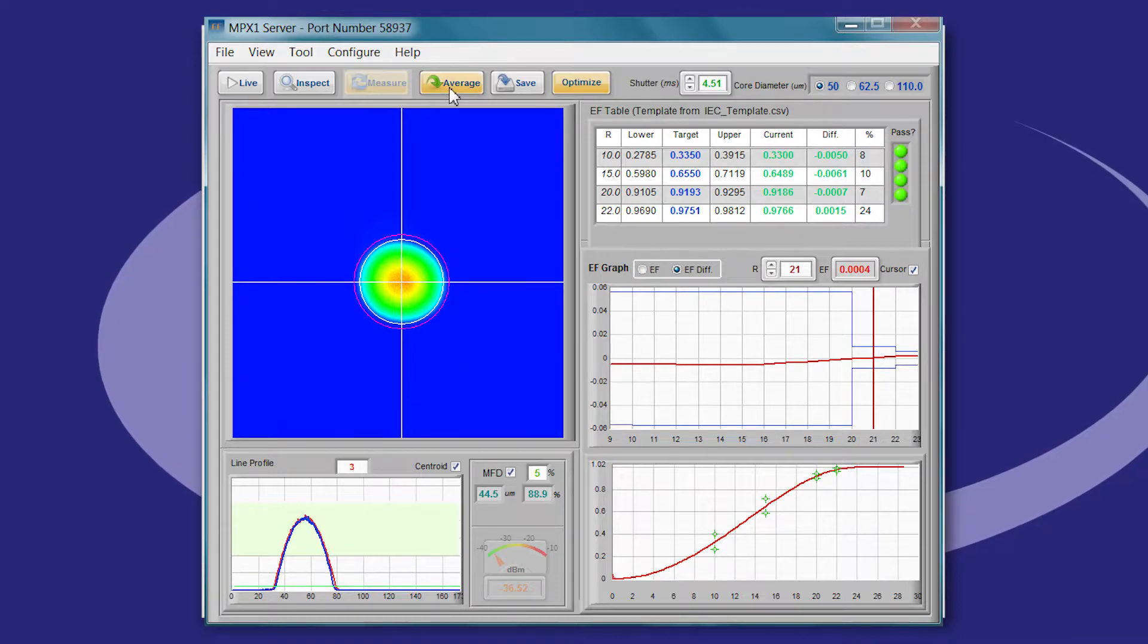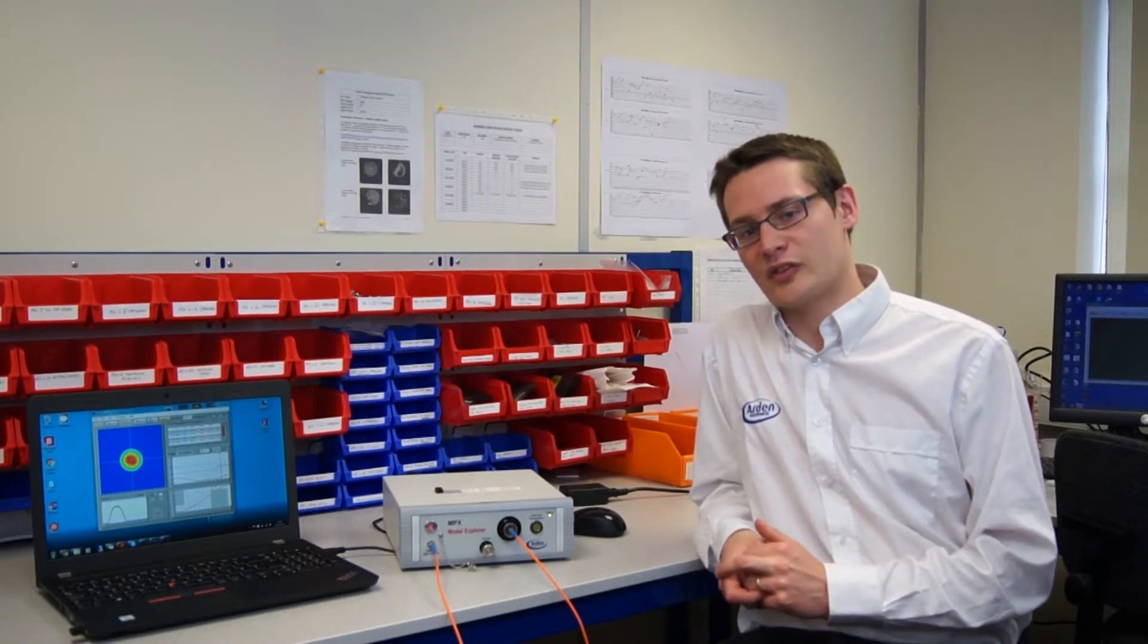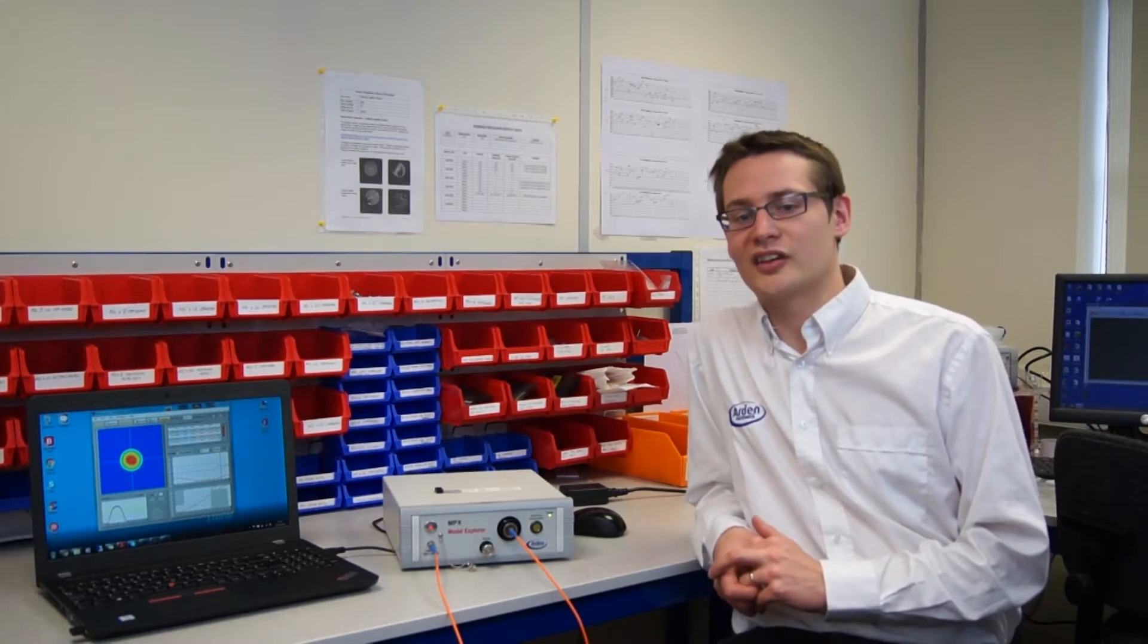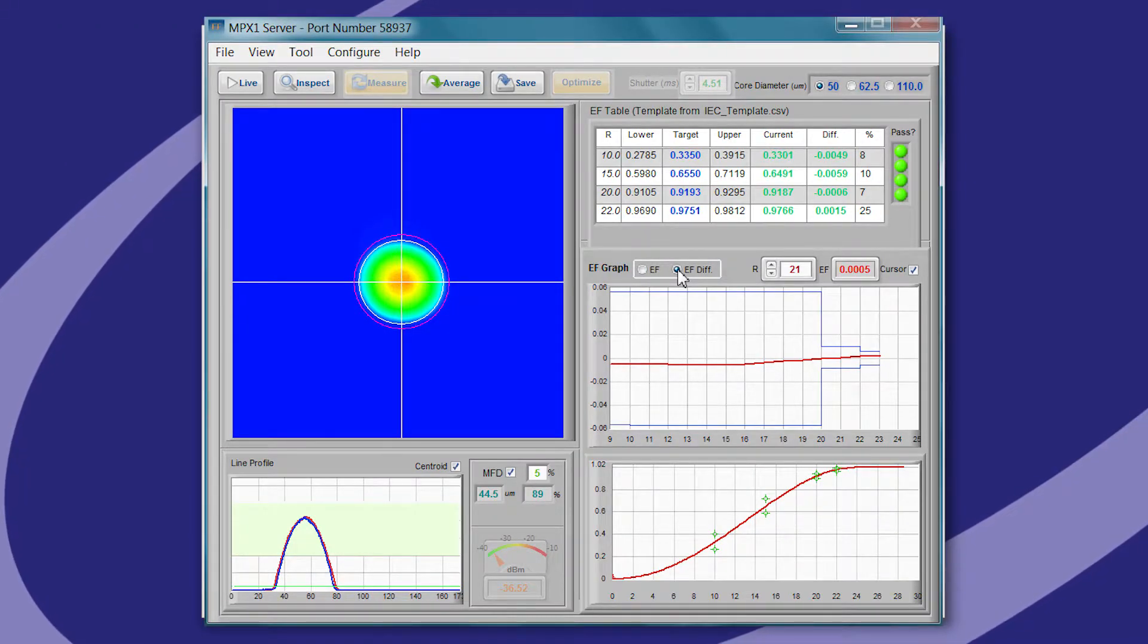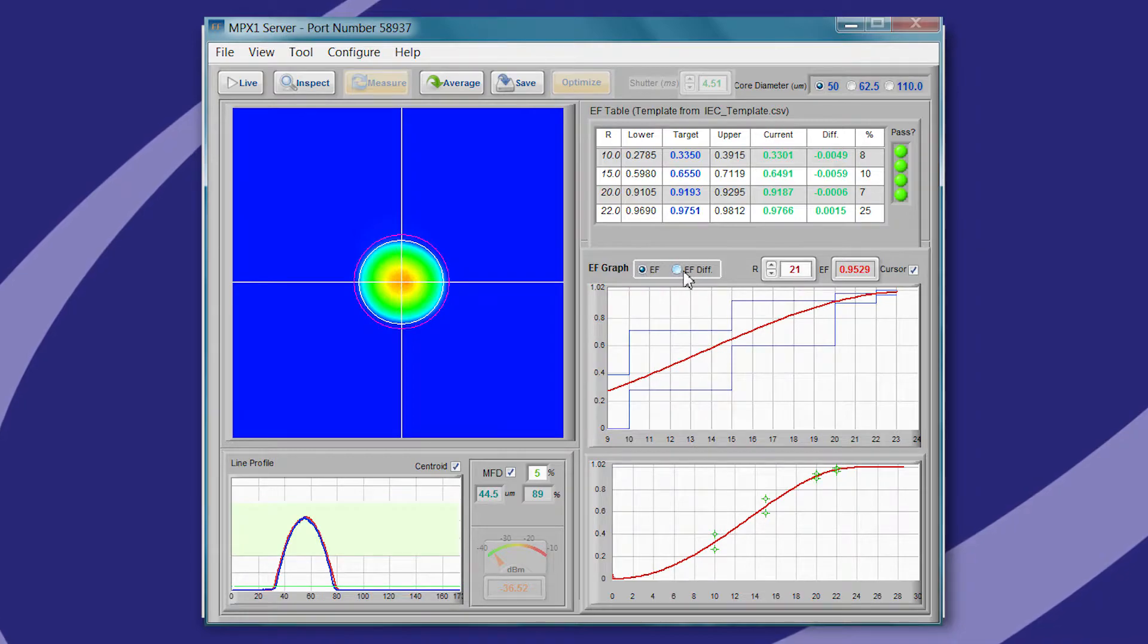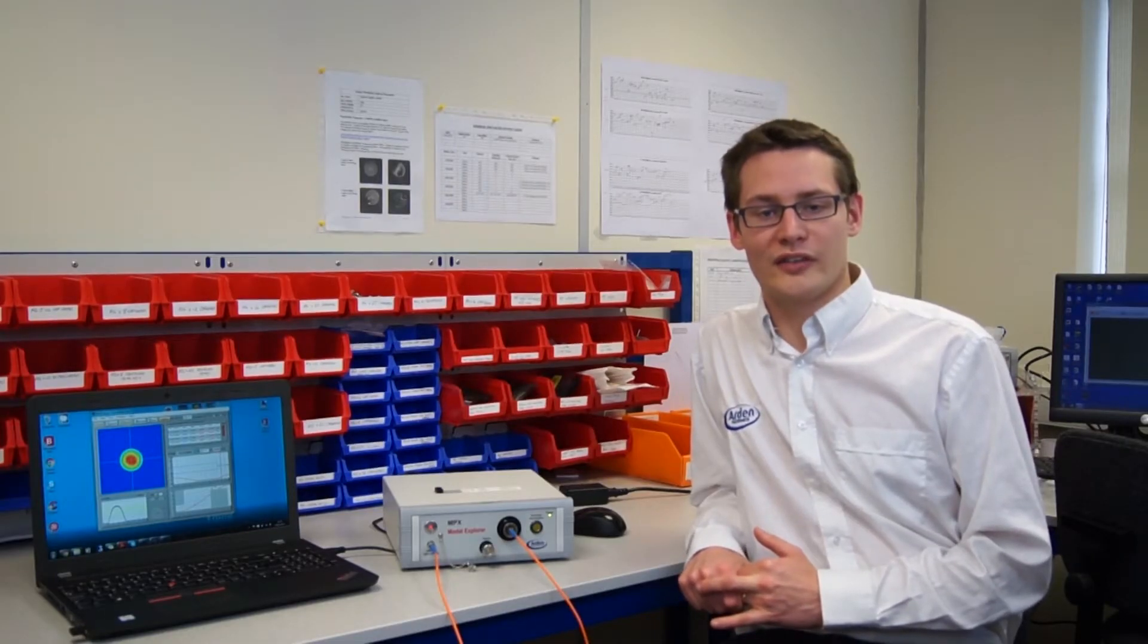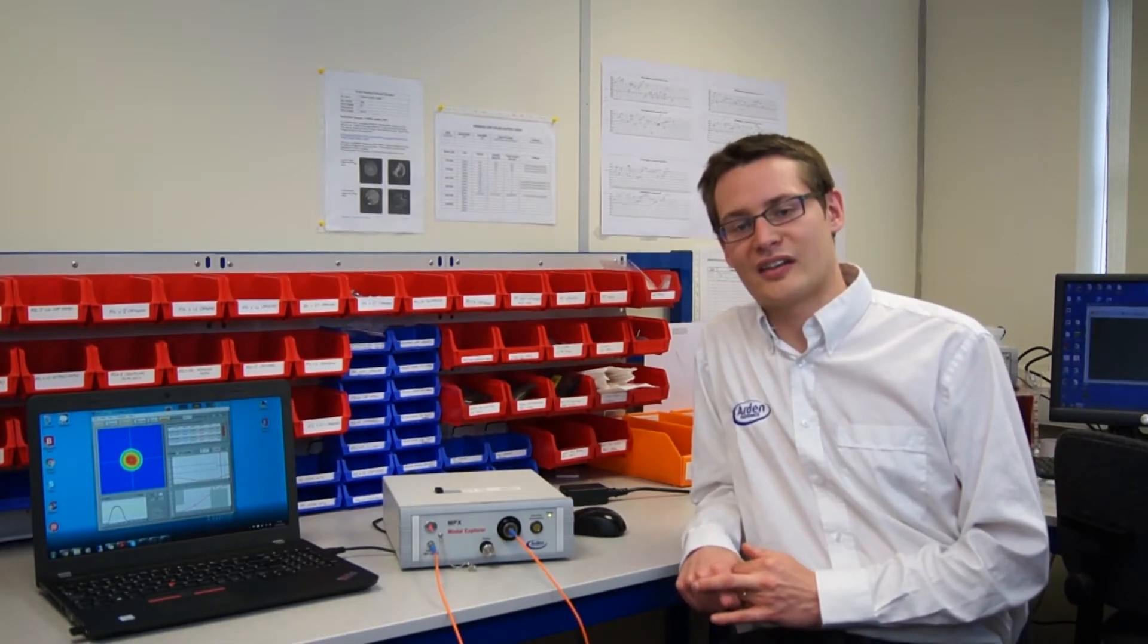Probably the biggest change is the addition of a new API functionality. This is a way for you to control and access data from the MPX programmatically. It enables automated testing and allows the incorporation of the MPX into integrated test routines. An additional license is required to use the API functionality. The API allows for the front panel functions of the MPX to be operated remotely. It comes with full documentation and sample code.